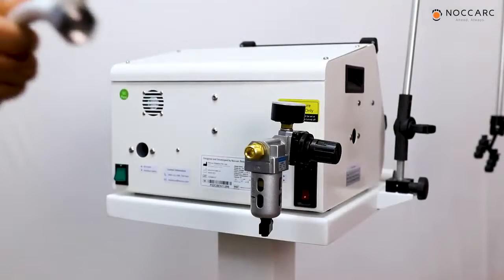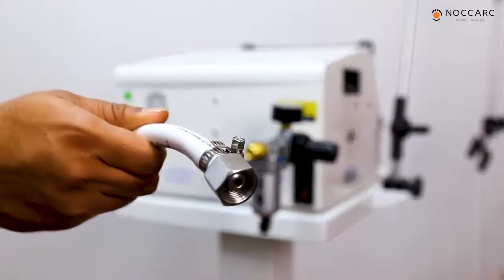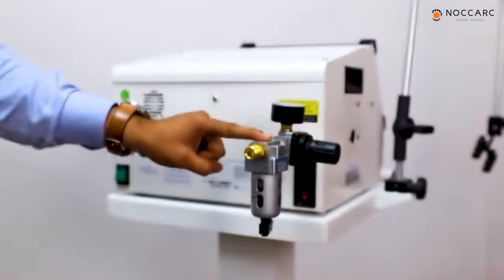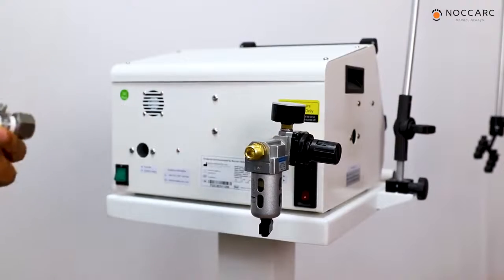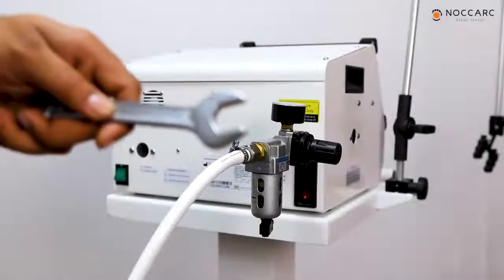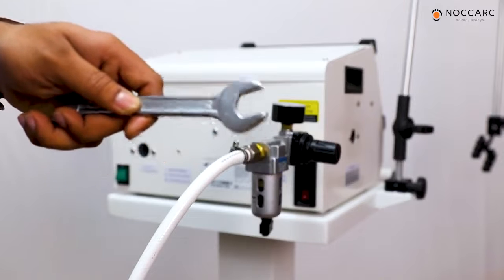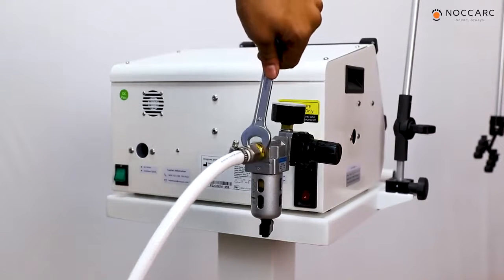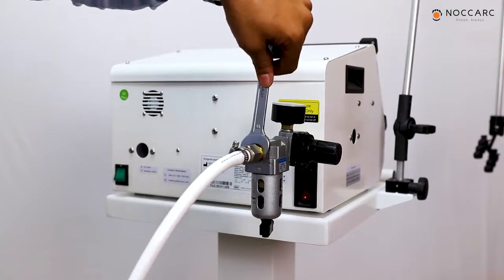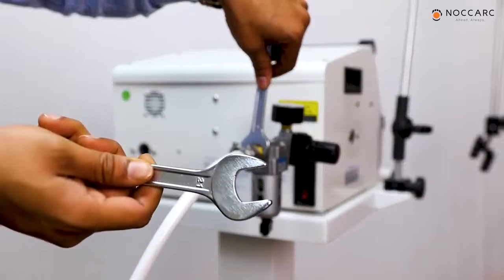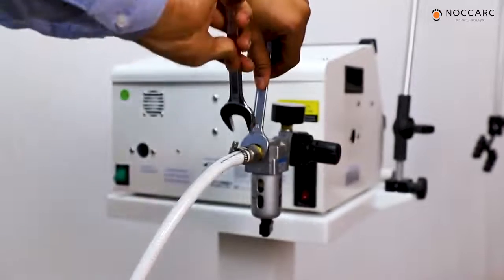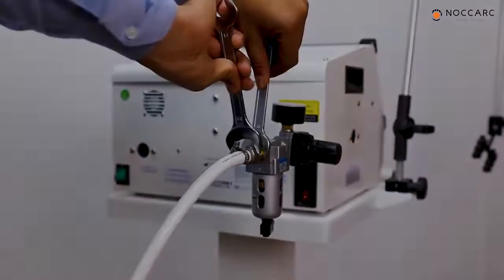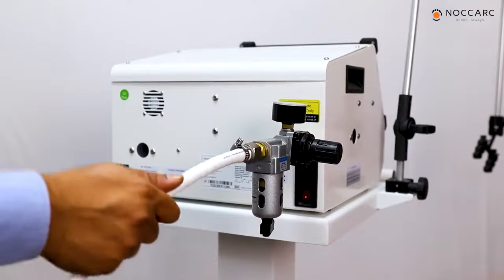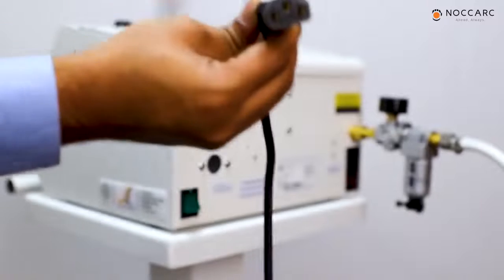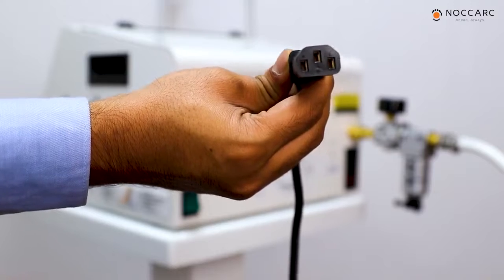Next step is buckle the oxygen hose ferrule connector on oxygen inline filter. Use spanners 18 mm side at oxygen inline filter's inlet. Use spanners 21 mm side to tighten the oxygen hose pipe. Ensure oxygen pipe is firmly connected. Plug single phase 3-wire cable at power socket.